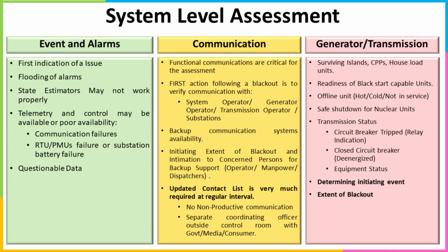So communication failure, RTU, PMU failure, and substation battery can even fail in case you delay. Although these are isolated, in case there is an issue and somebody has not checked the battery status for a prolonged time, the battery may not provide the desired DC output to power the breakers as well as your relays.